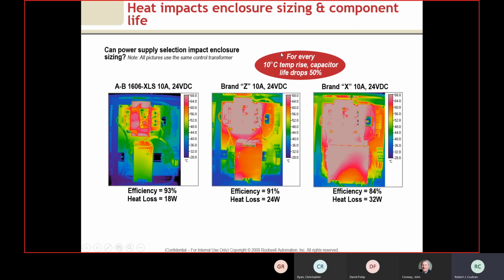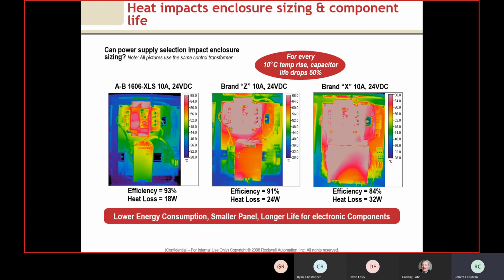This also talks about the amount of heat in the cabinet. A 10-degree C temperature rise drops the life of the capacitor by 50%. So we know heat kills, especially when it comes to a control panel. And so the goal is to keep this as low as we can so the components last as long as possible. We also know that the heat in the panel, for any of the end users who've had panels for a while, the heat begins to degrade the conductor cables. The plastic on them starts to degrade quickly with the heat, as well as a lot of the plastic components. So lower energy, smaller panel, longer life for the products, the components.